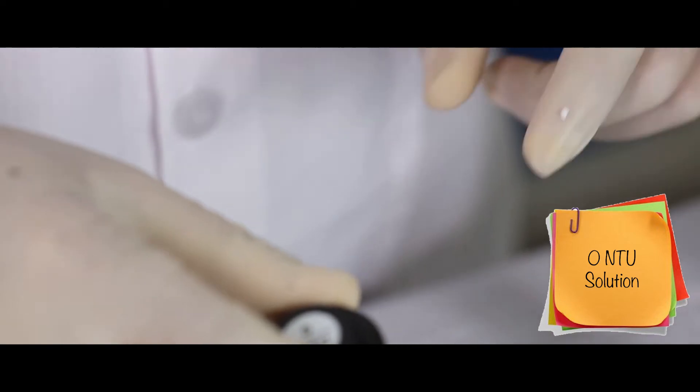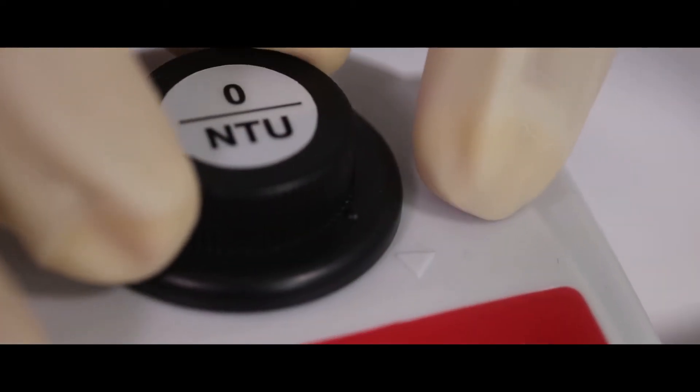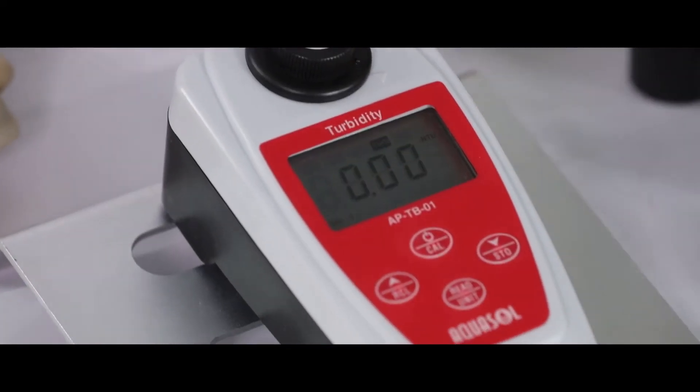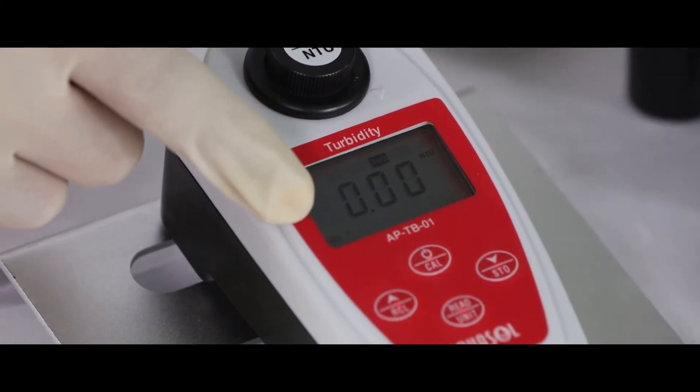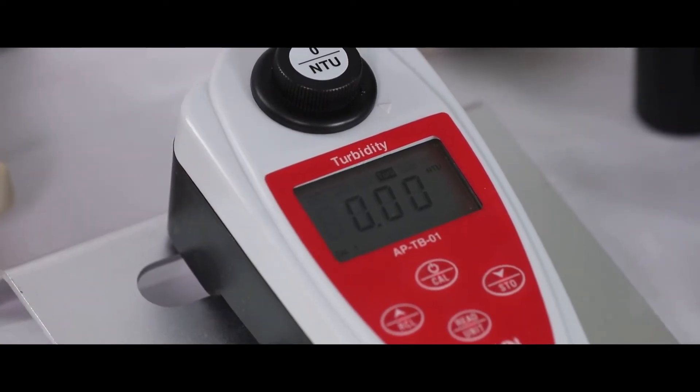Place the 0 NTU solution into the meter. Please make sure the notch on the meter aligns with the notch on the bottle. Press the read key to calibrate. The CAL icon will flash on the display. Once the meter is calibrated to 0.00...